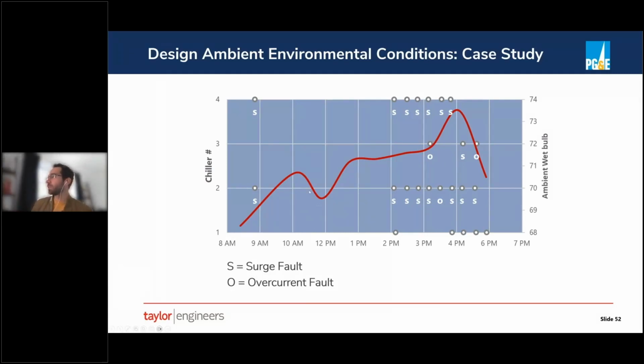issue. You can see on that day with the highest ambient wet bulb, this was essentially the sequence of events that they experienced. By 9 a.m., the wet bulb had already gotten high enough that it exceeded the design condition, and they had their first chiller surge fault. So essentially the chiller was operating at too high lift for the concurrent load condition. It couldn't handle it, and it tripped on a surge fault. So they had to manually restart the chiller.